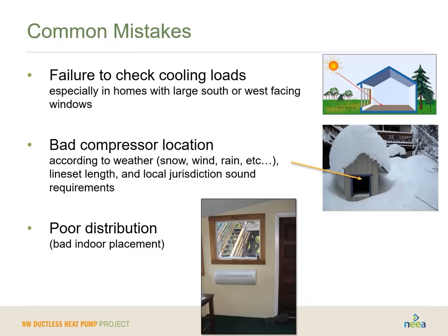Also, local jurisdictions have some sound requirements. Even though these are much quieter pieces of equipment, there are still some regulations out there. So making sure that the location of the outdoor compressor meets all local codes is also a good idea. And then with the indoor head, making sure that you're going to get good distribution.